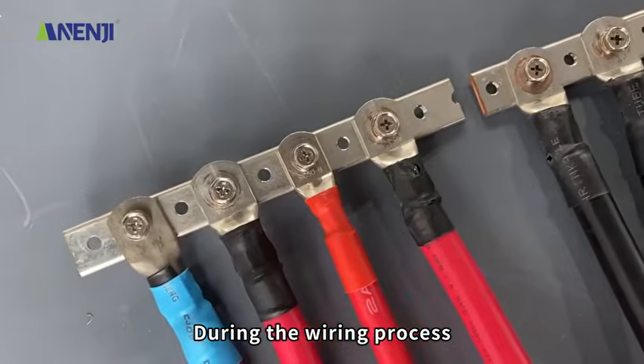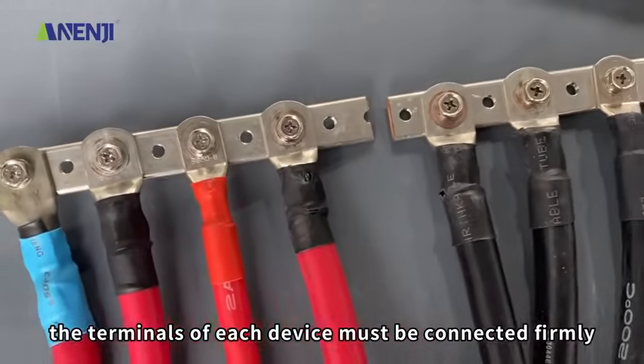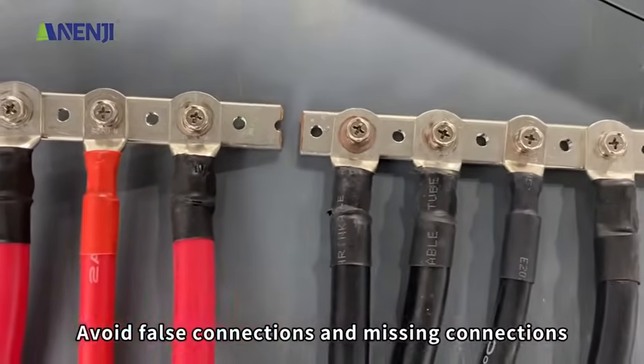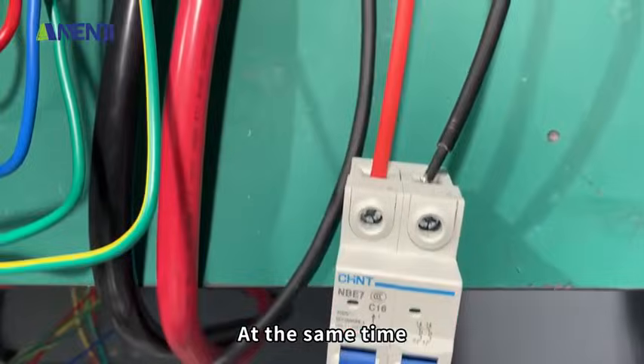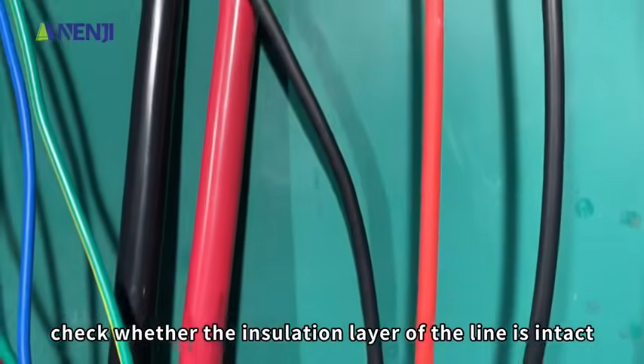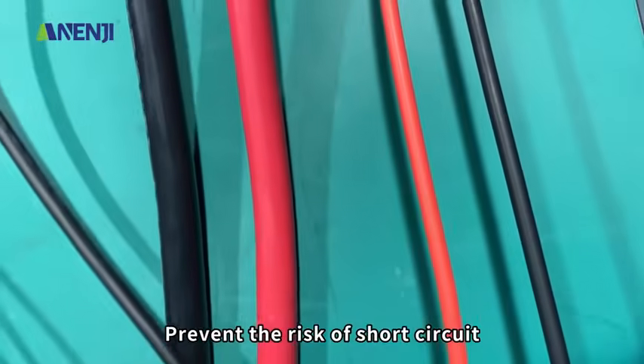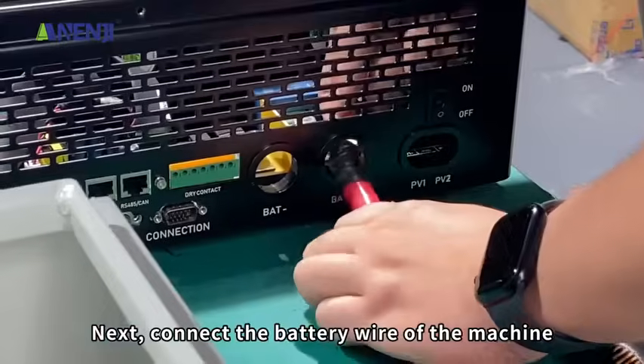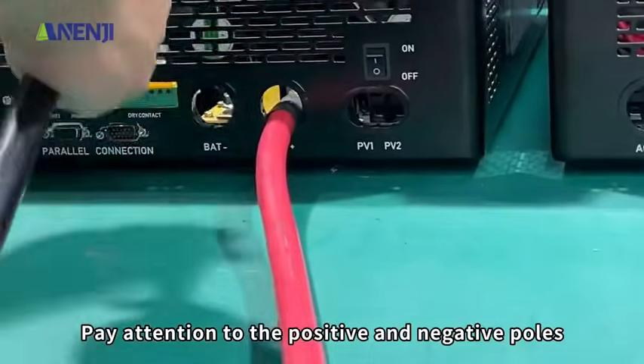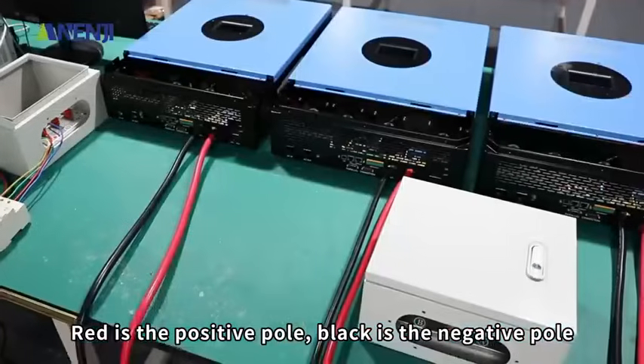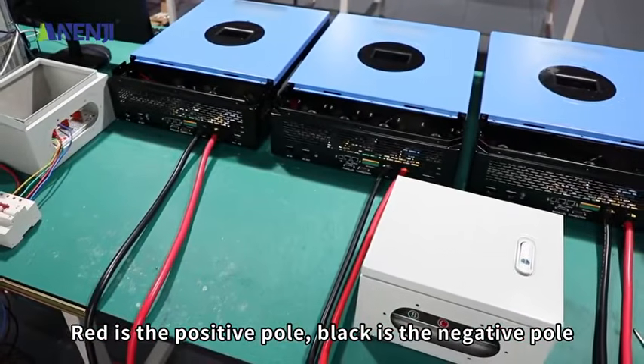During the wiring process, the terminals of each device must be connected firmly. Avoid false connections and missing connections. At the same time, check whether the insulation layer of the line is intact. Prevent the risk of short circuit. Next, connect the battery wire of the machine. Pay attention to the positive and negative poles. Red is the positive pole. Black is the negative pole.